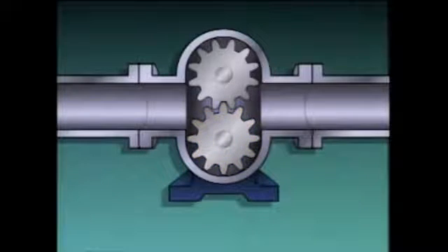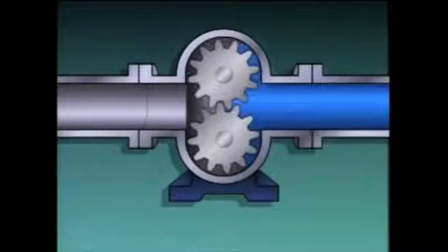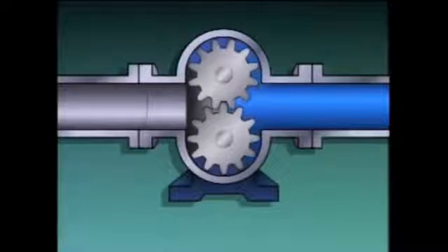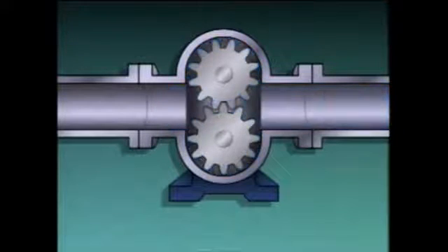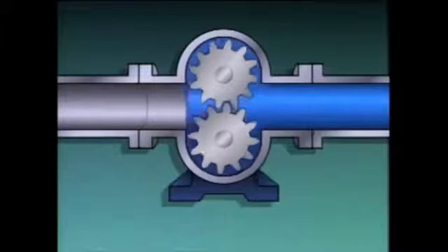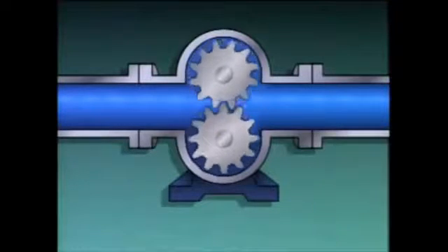During operation, liquid enters the pump through the suction port. As the gears turn, the liquid is trapped in the spaces between the casing and the gear teeth and moved along the casing. When it reaches the discharge port, it's forced out of the pump. Each space between the gear teeth positively displaces a given amount of liquid, so on each revolution that the gears make, a specific amount of liquid is pumped.